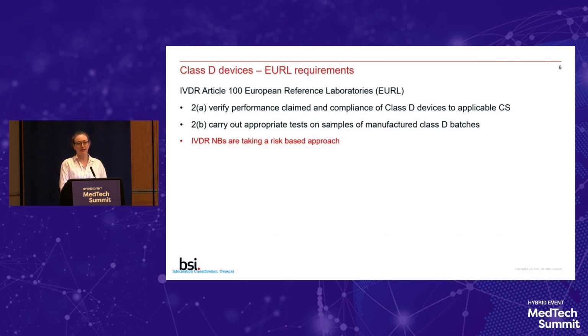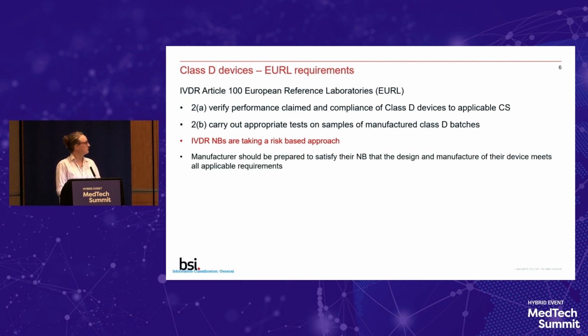All of the notified bodies are taking a risk-based approach now for issuing Class D certificates and for Class D conformity assessment. So the manufacturer really needs to be prepared to satisfy us that the design and manufacture of their device meets all applicable requirements. We're taking a big step without the reference laboratories, so manufacturers should be really aware that for notified bodies this is a high-risk activity and the onus is on the manufacturer to really present a lot of clear, robust data for the conformity assessment process.